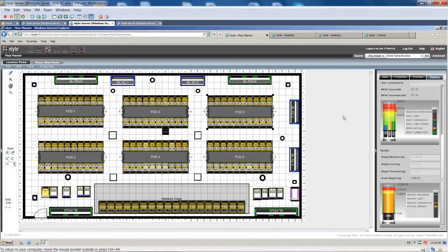The heat and weight gauge are showing me, for user-defined thresholds in those areas, how am I doing against the capacity. In the heat gauge, I see 3 bars. The left bar in blue there is showing me based on real-time metrics collected for that area, and then the yellow and green bar are as models. How is my consumption of heat and cooling capacity against the thresholds for that area holding up.